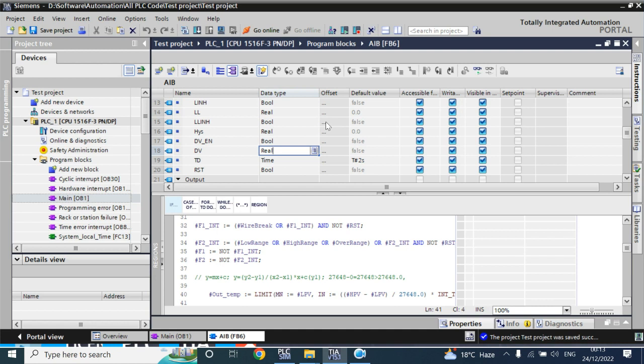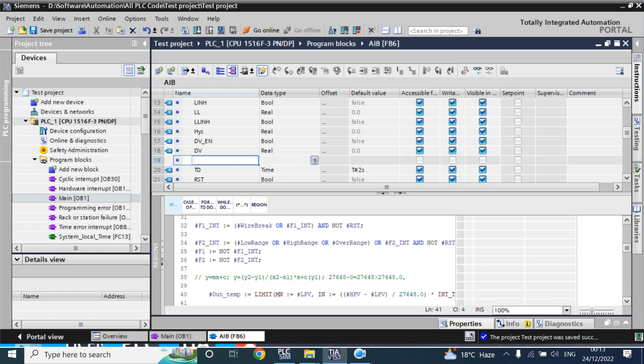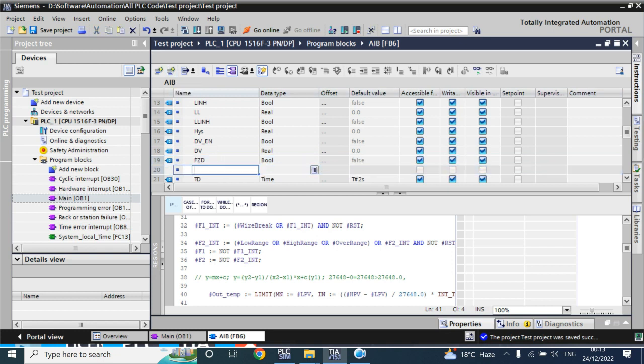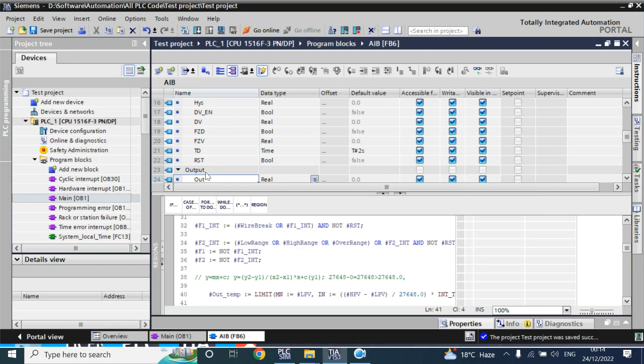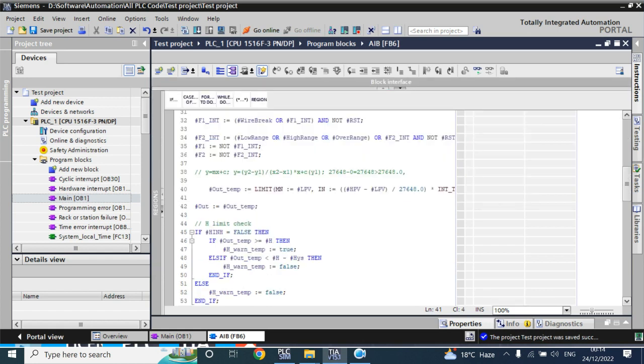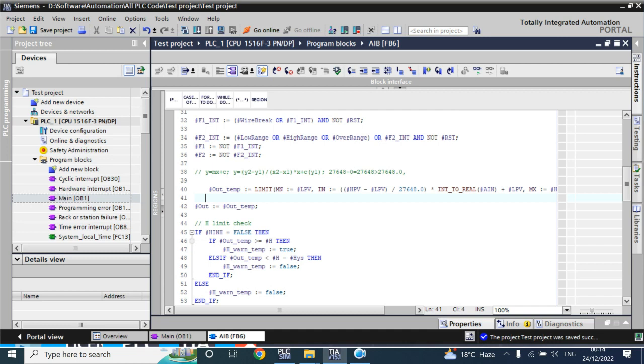For the case of wire break, low range, or high range, we will take another variable and name it 'freeze' — this is a boolean tag. This freeze variable will copy the frozen value to the output real value. By this freeze option, the frozen value is copied to our output variable, and you can remove your signal — it will not create any alarm; it will hold by this frozen value.